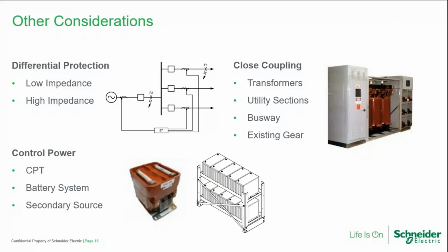Close coupling is an important thing to consider. With gas insulated switchgear, I'm not aware of any close coupling capability. With solid insulated switchgear, some allow it, some don't, so it's more prevalent with cable connected designs. And then control power is an important thing to consider. With these newer styles of switchgear, a lot of times you don't have the option for a CPT. So we need to make sure that we're designing for control power either from a downstream panel, the secondary of a transformer, a battery system, if that exists in your design, or maybe a UPS somewhere in the design. So we just need to make sure that's part of the design consideration.